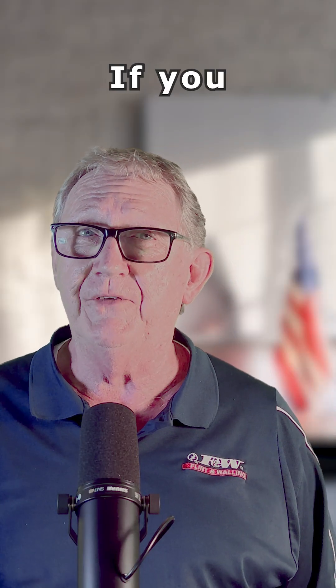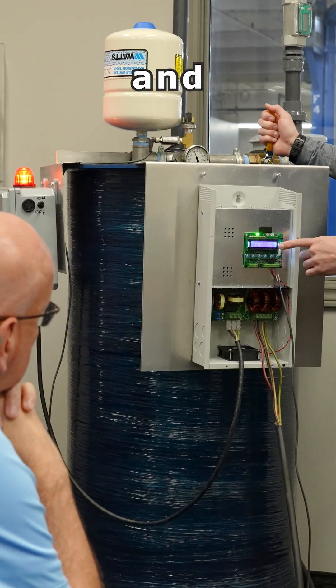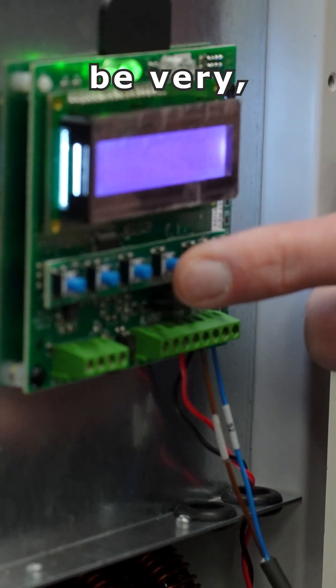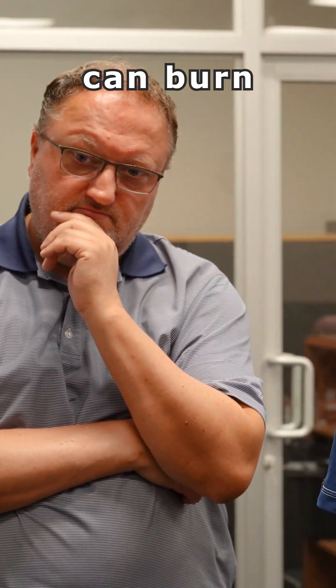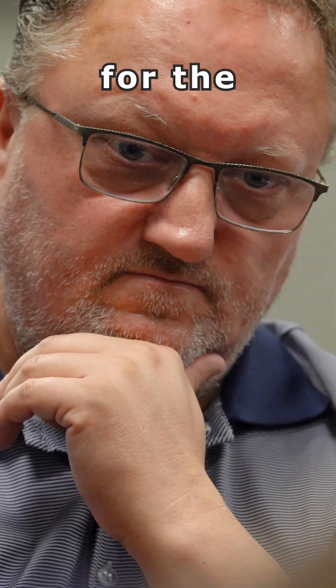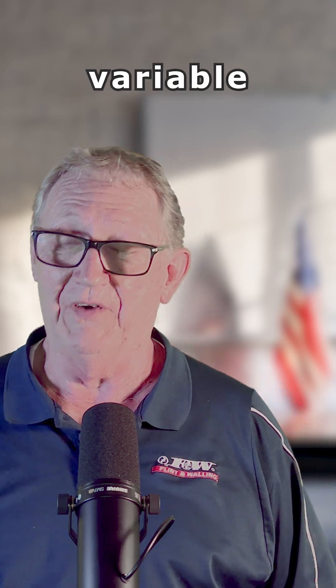But I will tell you this: if you sell variable frequency drives — VFDs as they're commonly referred to — a megohmmeter investment would be very, very important. Because these drives have voltage spikes, and sometimes that can burn right through a wire or cable that is not properly sized for the application. A megohmmeter is going to give you that information to determine that on a variable frequency drive.